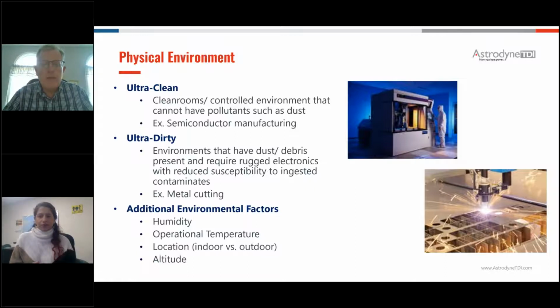You have to watch out, you can't emit pollutants into the external environment. Likewise, there's other environments, such as a metal cutting floor, where there can be a lot of dust and debris floating around that could cause power supply reliability issues if the power supply ingests that material. So having a supply that doesn't have impingement of external air on its internal components can be a real advantage in those applications. Alongside those, environmental contaminants like humidity, especially in some equatorial regions, can really be an issue with regard to power supply reliability.